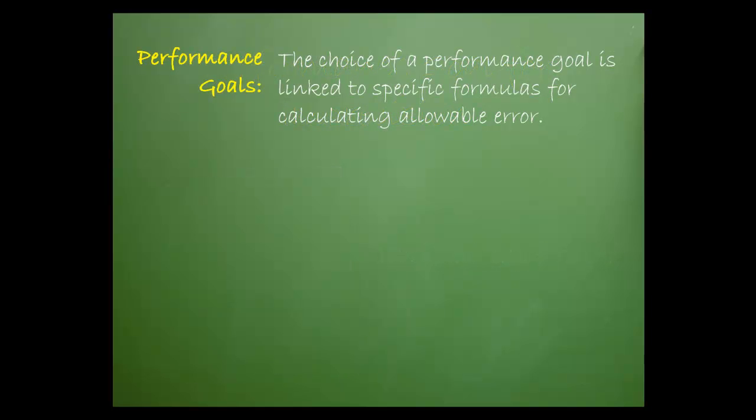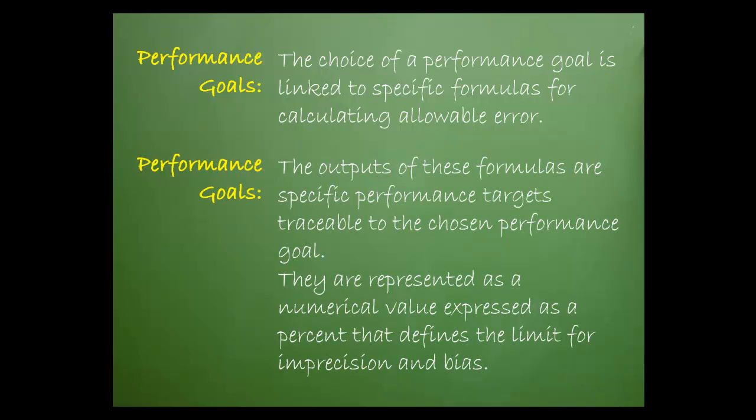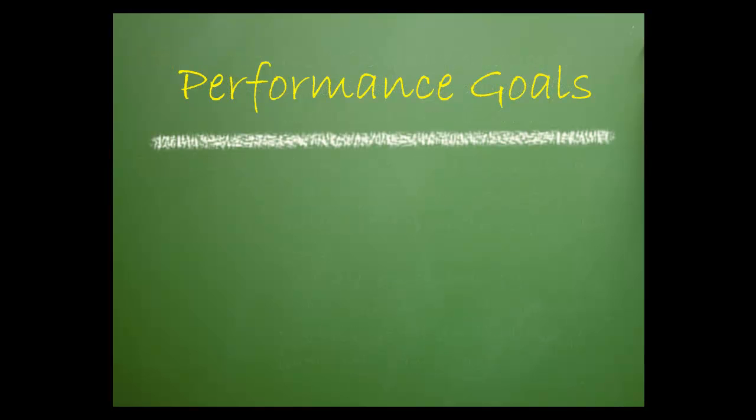The choice of a performance goal is linked to specific formulas for calculating allowable error. The outputs of these formulas are specific performance targets traceable to the chosen performance goal. They are represented as a numerical value expressed as a percent that defines the limit for imprecision and bias. There are three performance goals from which the laboratory can choose: minimum, desirable, or optimal.